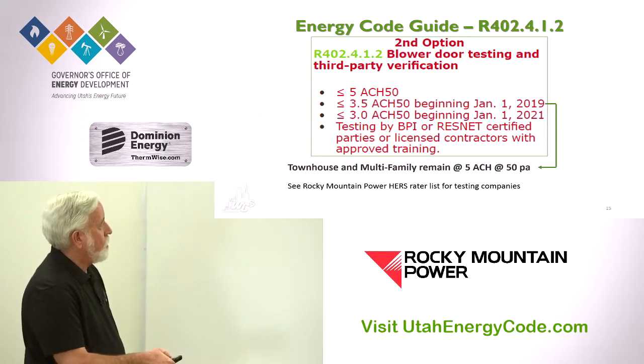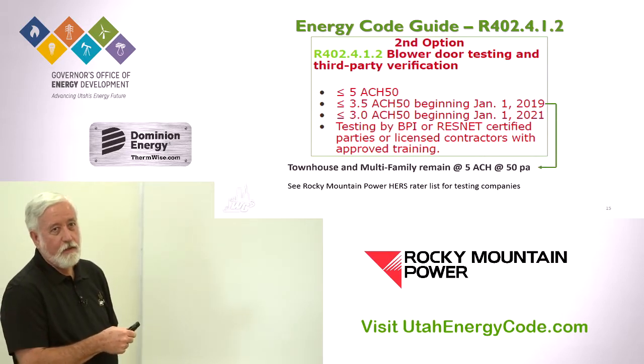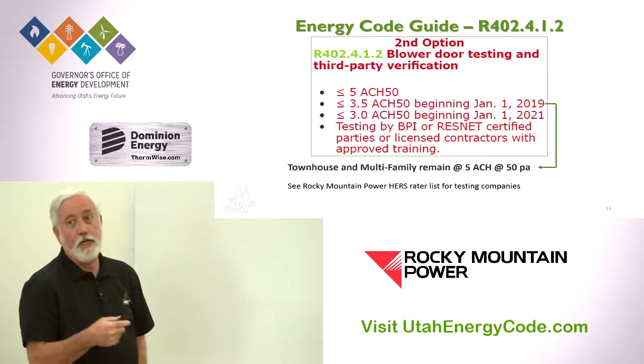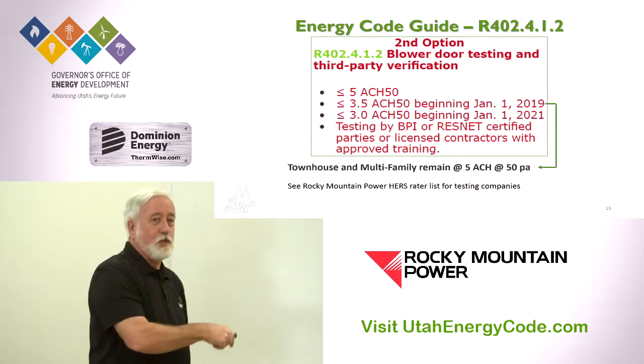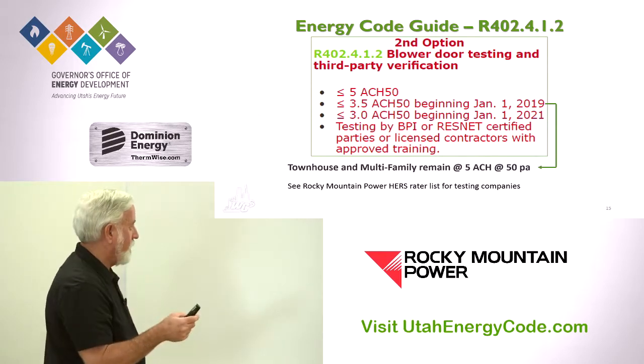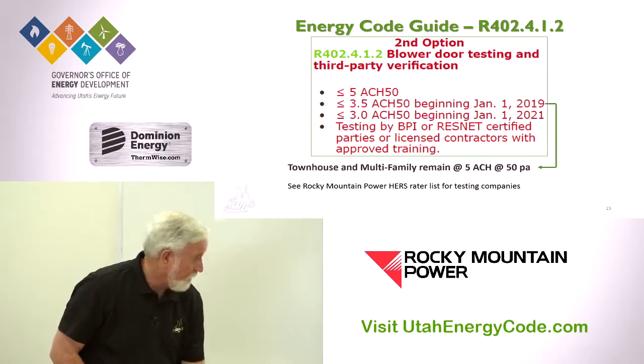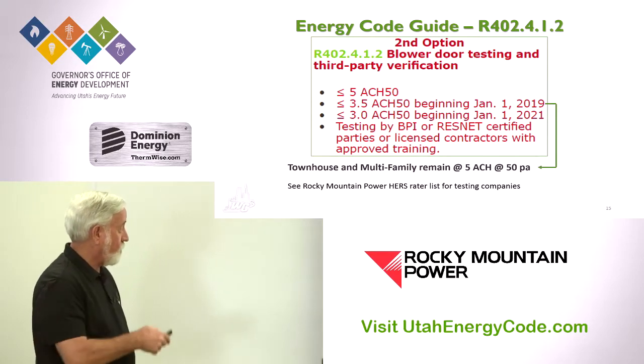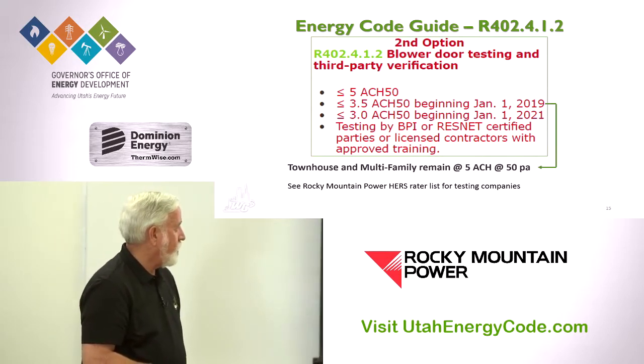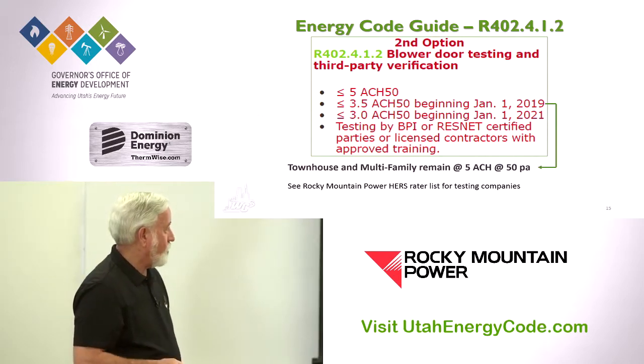So the section options are either the comprehensive inspection or the blower door test. As of January 1, we have to be down to 3.5 air changes per hour at 50 pascals — approaching the three air changes per hour — so we really should be planning on doing mechanical ventilation to play it safe. Townhouses remain at five air changes per hour. You can see Rocky Mountain Power for HERS Raters, or go to utahenergycode.com for a list.